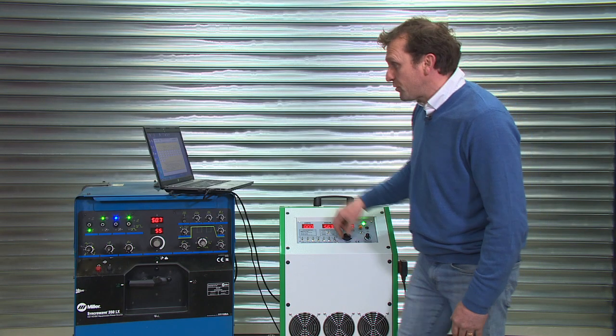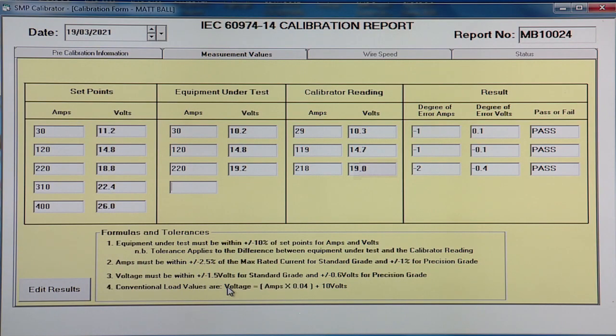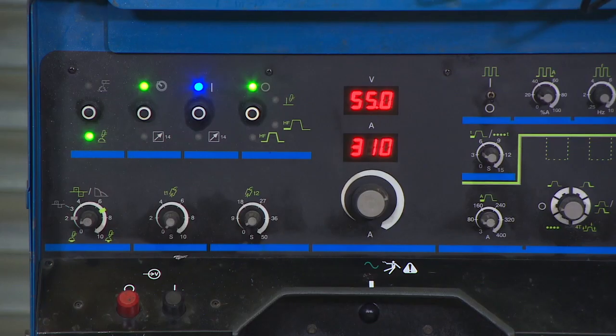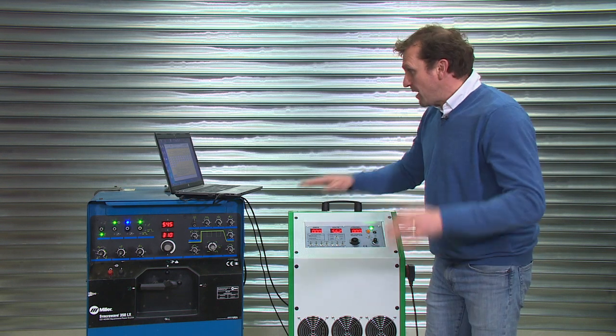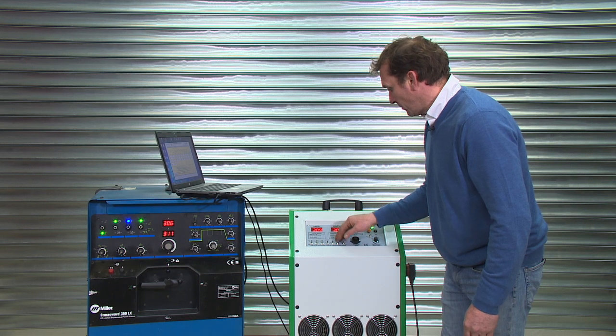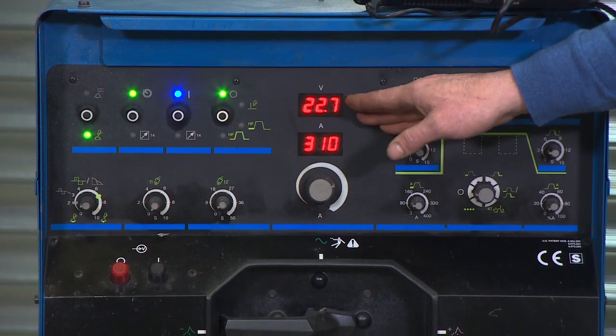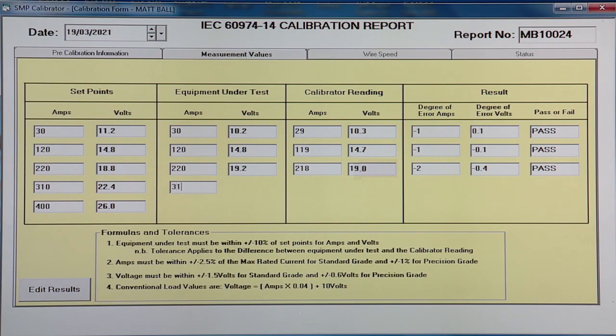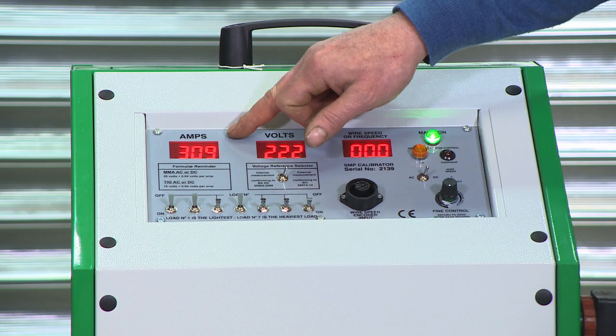Then we'll move on and take our next reading, 310 amps and 22.4 volts. Set the welder to 310. Then we'll load the calibrator to read around the 22.4 volts. So we have the welder reading 310 amps, 22.7. We enter that into the program. And then we fill in the calibrator reading, 309 and 22.2.